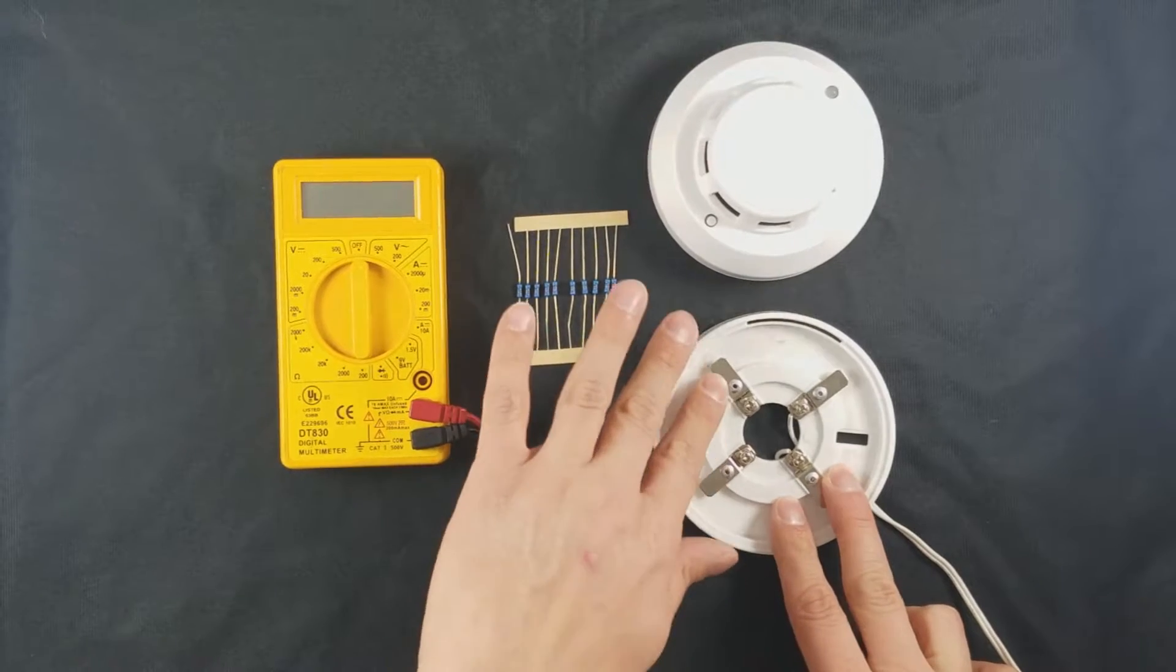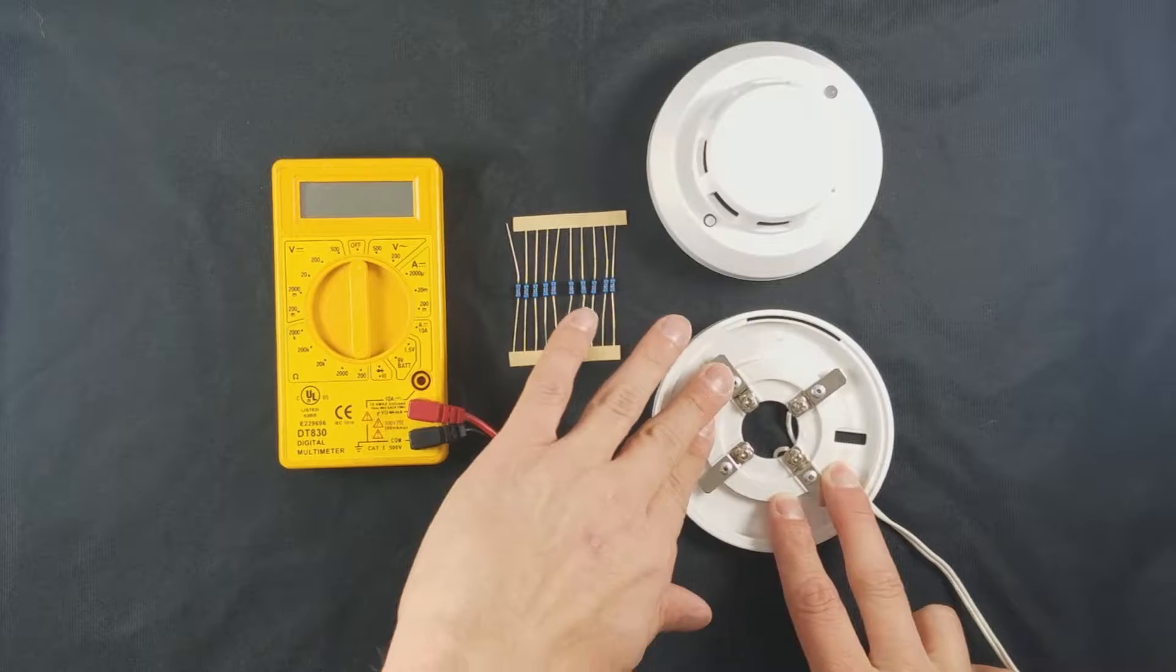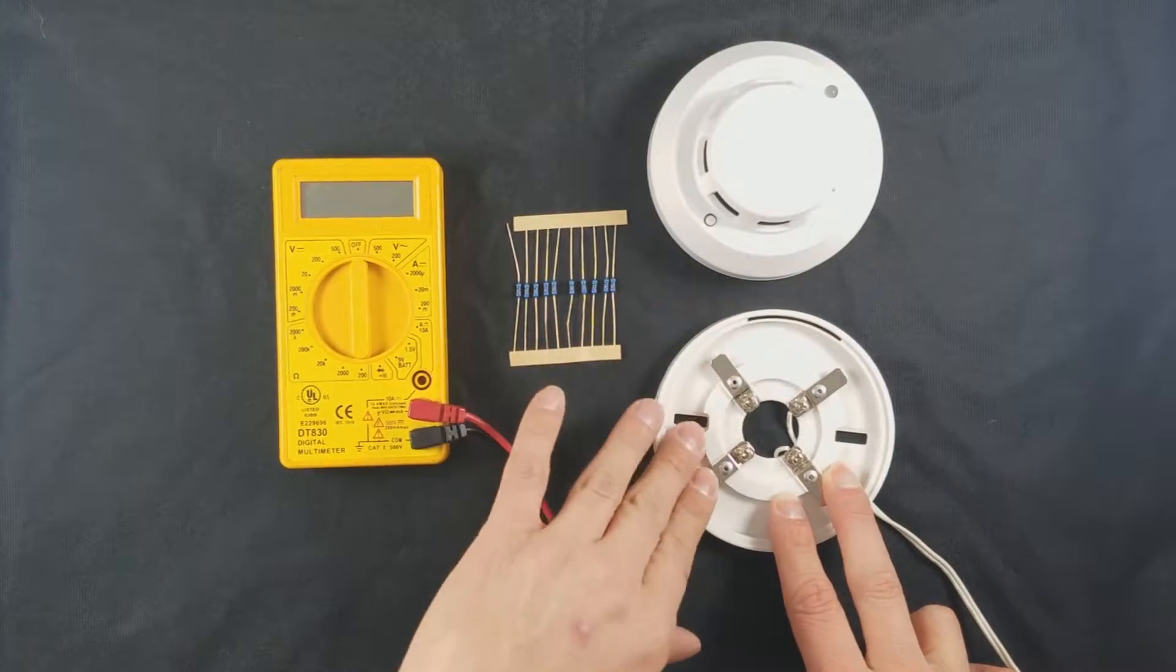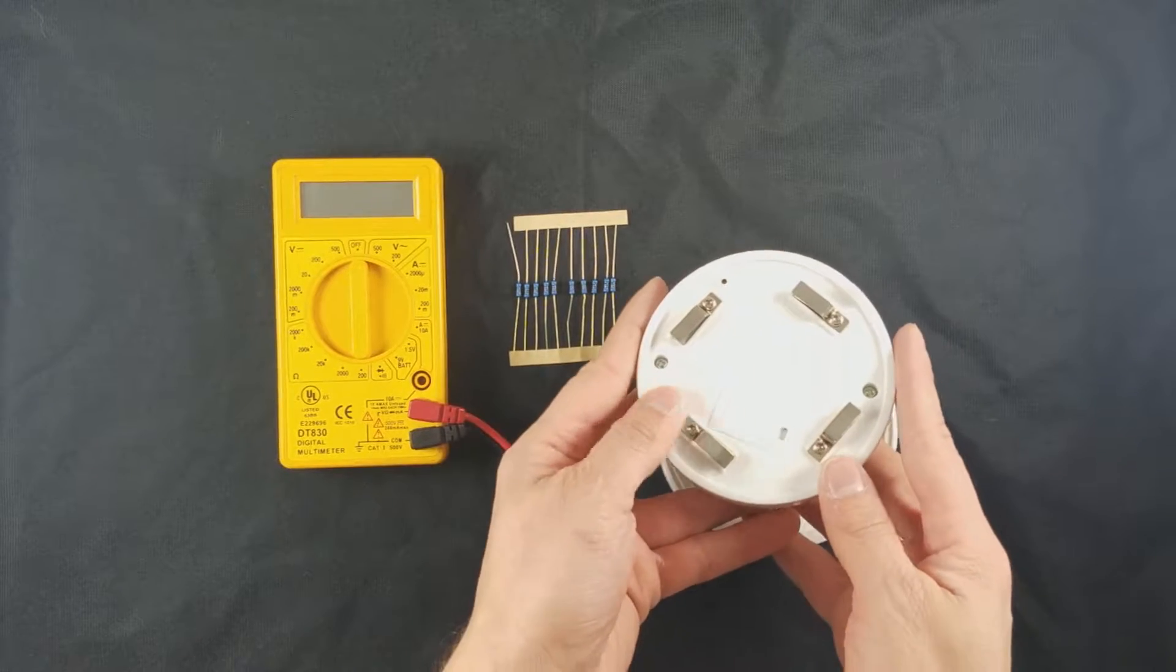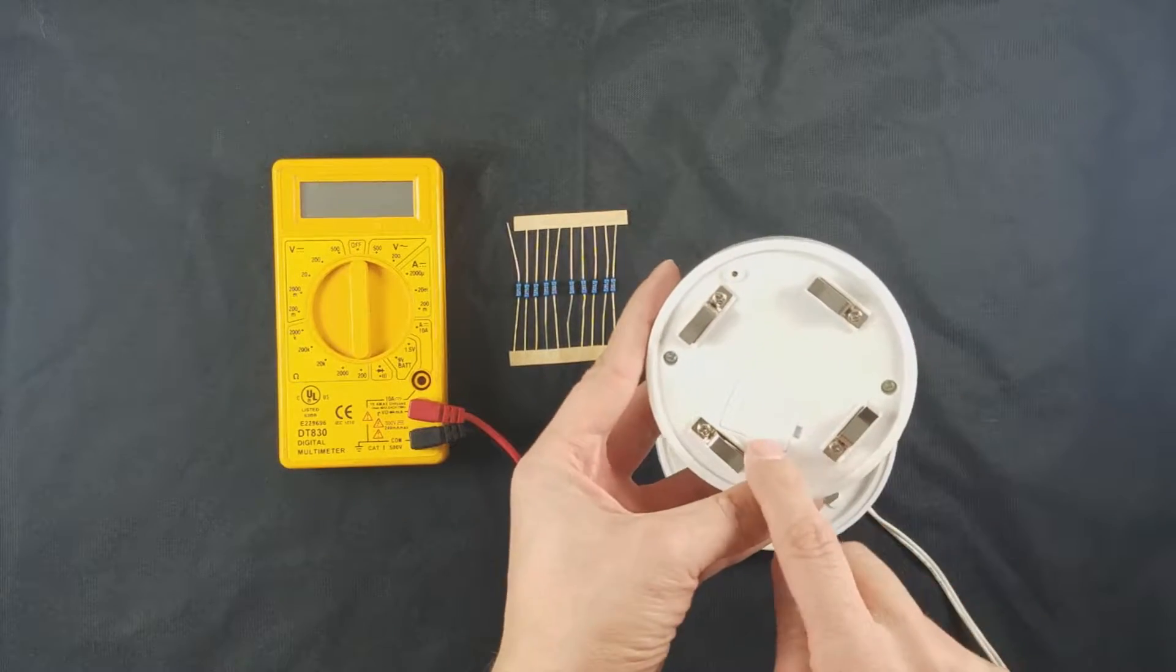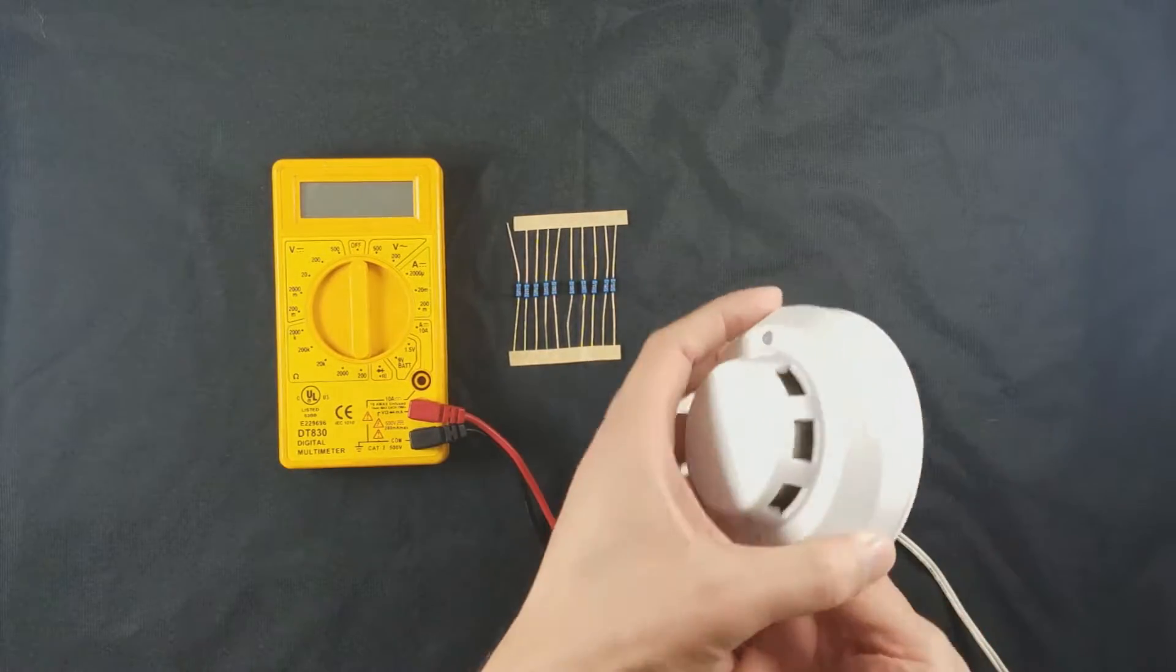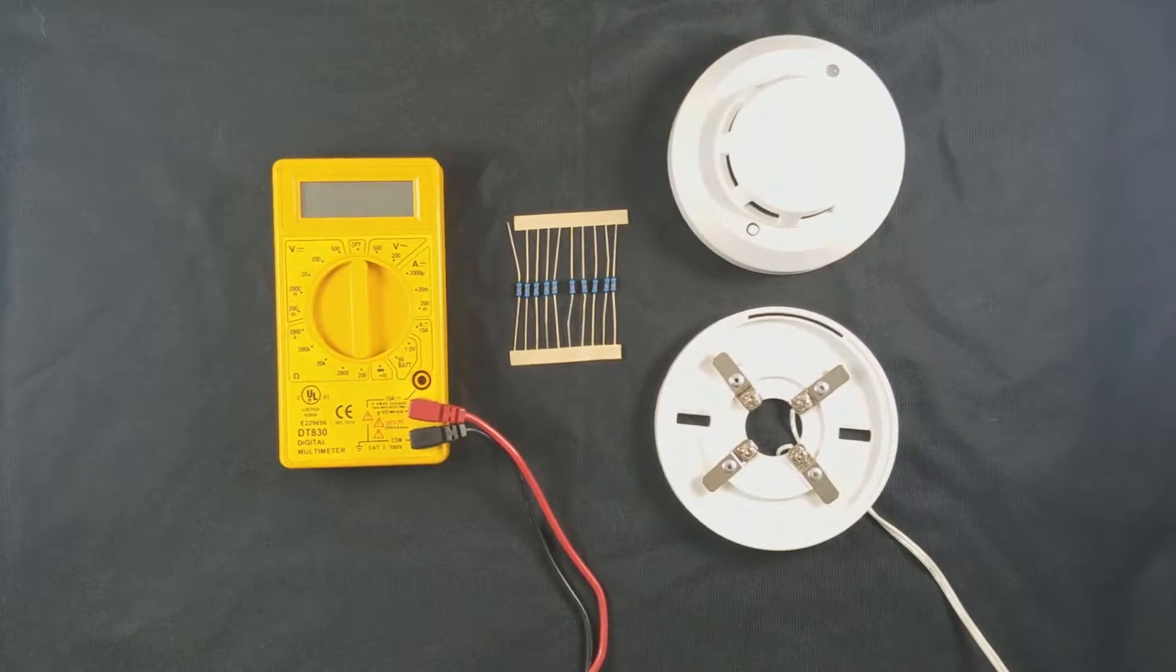Terminals 2 and 3 are your relay circuit, which can be normally open or normally closed. There's a selector on the back of the smoke detector under this cover where you can choose between normally open or normally closed.